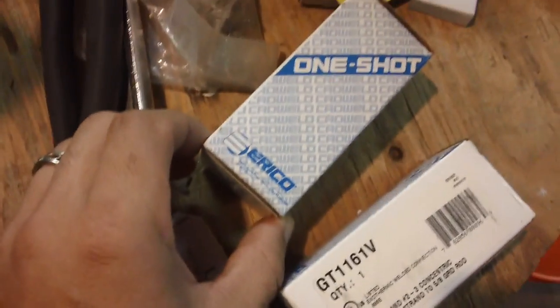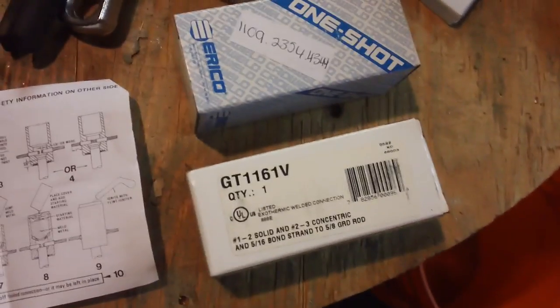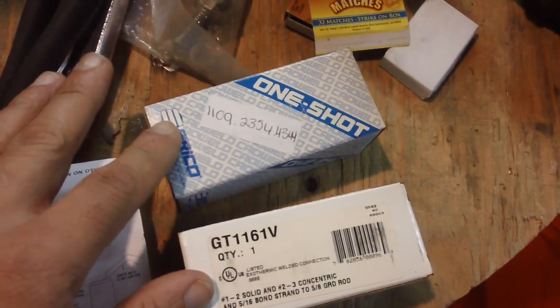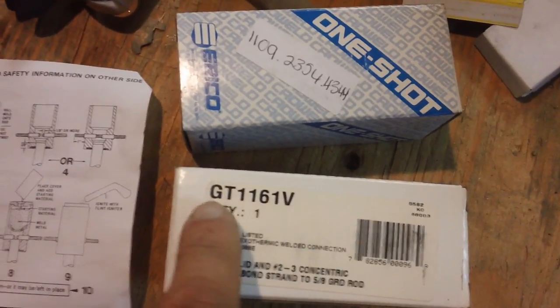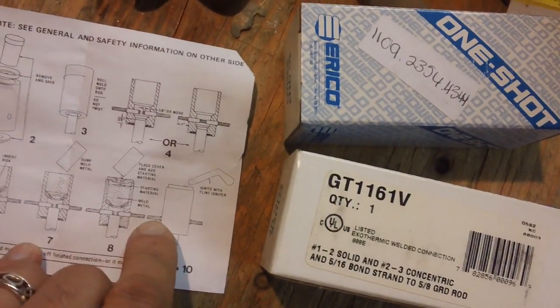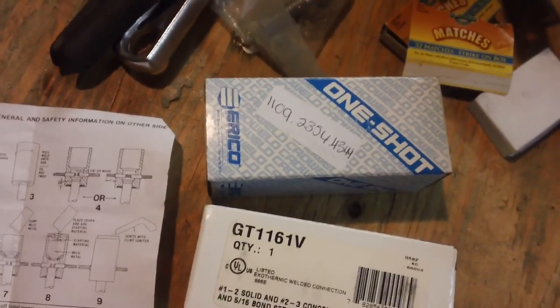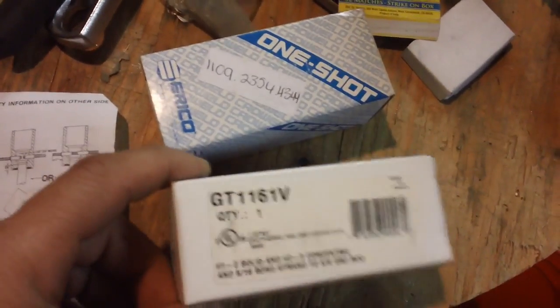The company that makes it now is called Erico. These two examples I got on eBay — they're really cheap there, about eight dollars each. I bought a lot of four, so I was able to ground four grounding rods. You'll see various part numbers for a one-shot, and what that means is the size of cable it will accept and the size of the grounding rod, which varies from half-inch to three-quarters to five-eighths inch, and cable from two gauge to four gauge.